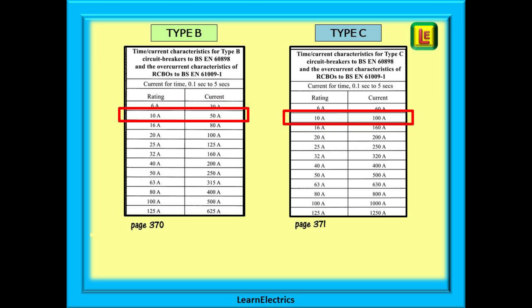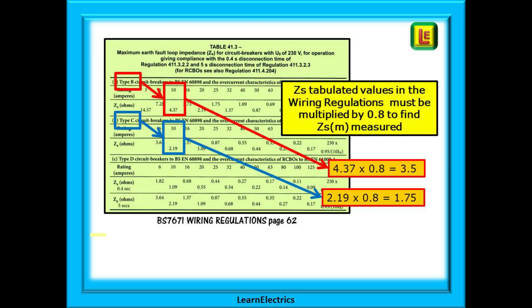Look at the red highlighted boxes. The chart actually tells us that the fault current required for a 10 amp B type is 50 amps and for a 10 amp C type it is 100 amps. If we make some calculations on these numbers we arrive at the maximum permitted ZS for each type and these are shown in our case on page 62 of the wiring regulations. The red boxes show the B type as having a maximum ZS of 4.37 ohms and the blue boxes show the C type has a maximum ZS of 2.19 ohms, half the B type maximum. We've halved the sensitivity so we must halve the ZS and these tables tell us this.